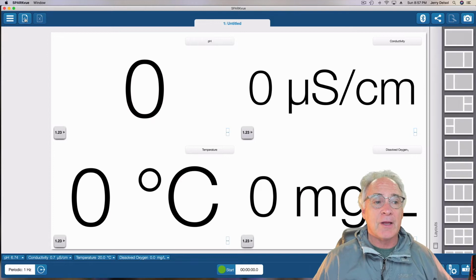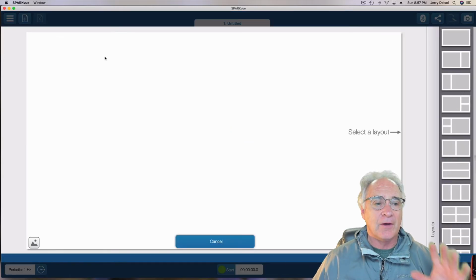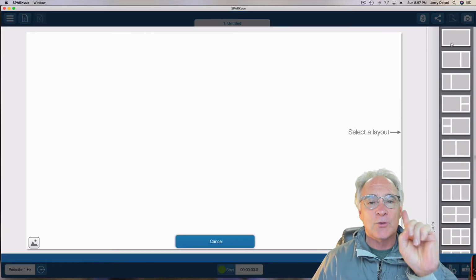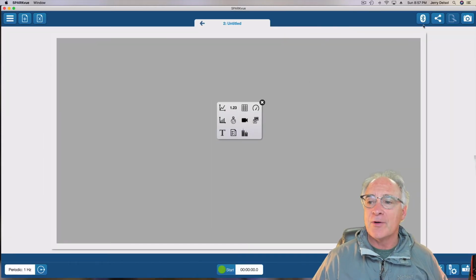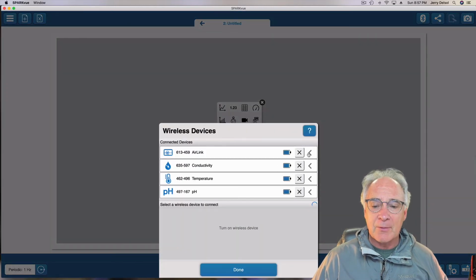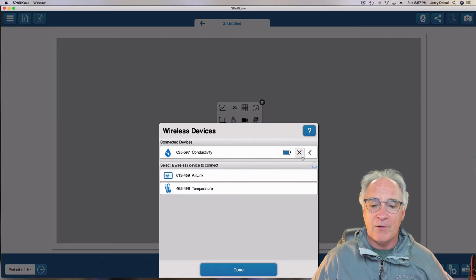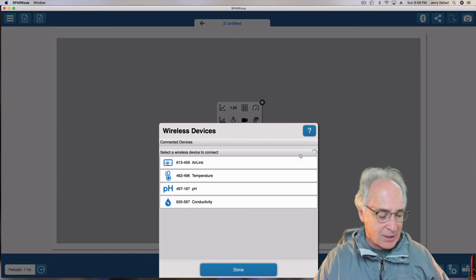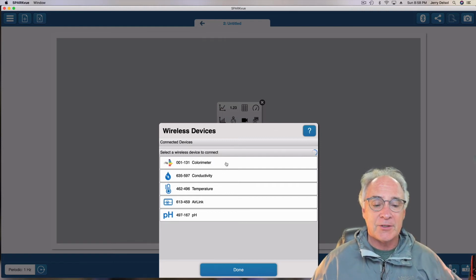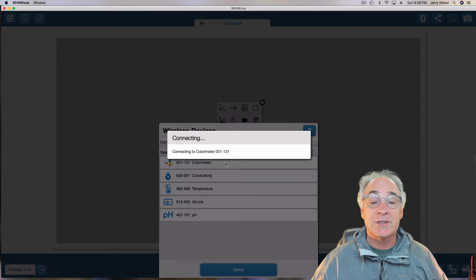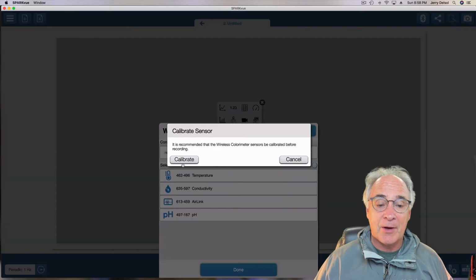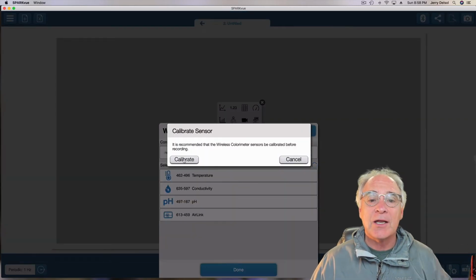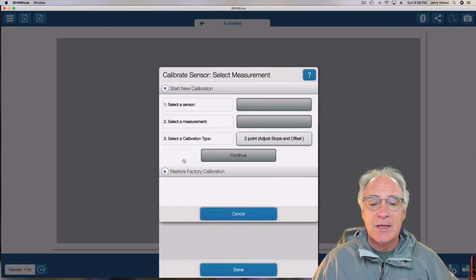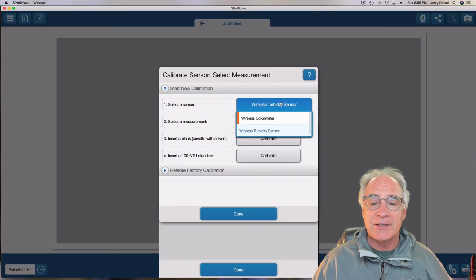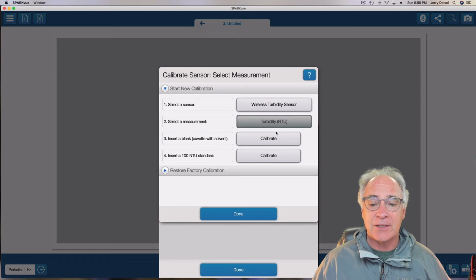Now to do that, I'm going to separate a different type of template that just has the 1 page. That should be able to handle it pretty well. I'm going to click on this, and then I'm going to take everything off of it. Now, because it's been sitting here, it needs to be turned back on. Right, now the colorimeter turbidity sensor is ready to go, so we're going to click it once, and we're going to upload that by pairing it. But we first of all have to calibrate it. So click on the calibration button, and then you select the sensor, and that is the turbidity sensor.